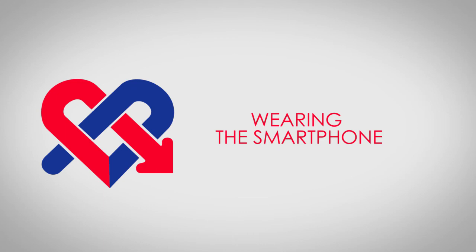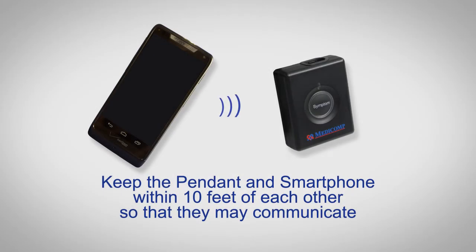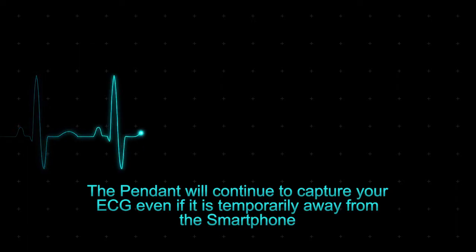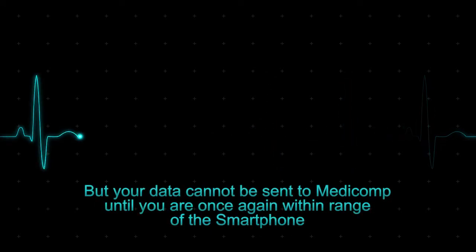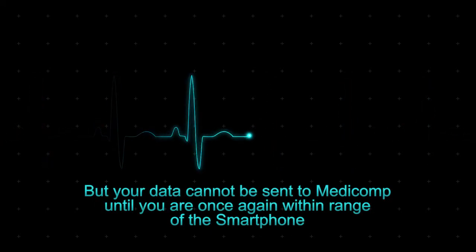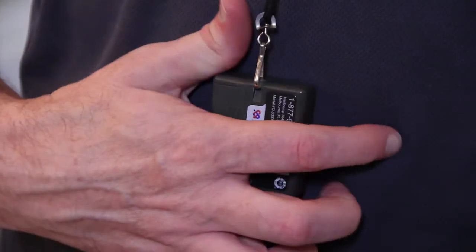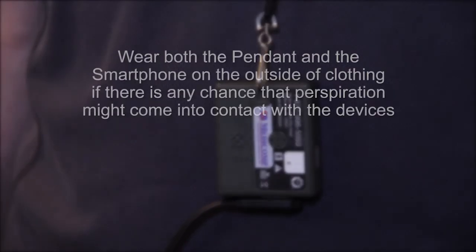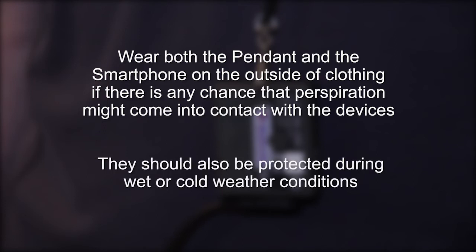Wearing the smartphone: it is not necessary to always keep the smartphone on your person, but keep the pendant and smartphone within 10 feet of each other so that they may communicate. The pendant will continue to capture your ECG even if temporarily away from the smartphone, but your data cannot be sent to Medicomp until you are once again within range. Both the pendant and the smartphone should be worn outside your clothing if there is any chance that perspiration may come in contact with the devices, and they should be protected during wet or cold weather conditions.